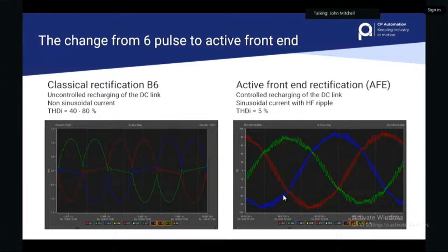Here I'm giving a prime example that we use with our meter to show you the difference, for those familiar with variable speed drives that create harmonics, of a B6 bridge, which is a standard drive that you would buy, be it Siemens, Rockwell, ABB, doesn't really matter who they are. And on the right-hand side is what we call a low harmonic drive, or AFE. On the left-hand side you can see that we have these humps on the waveform. This is the distortion that's going to the transformer. So we want to get rid of that.